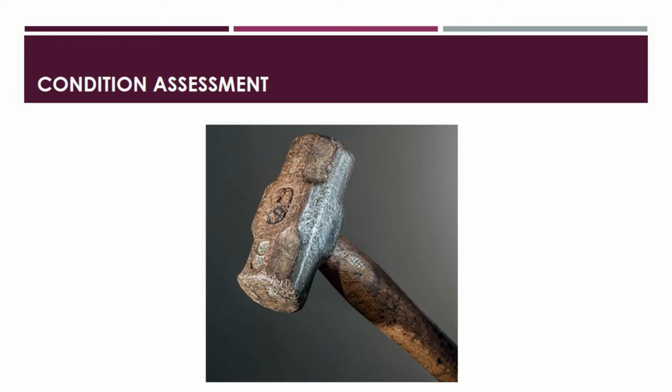Instrumented hammers record and analyze the vibration created by a hammer blow and discover patterns that indicate the severity of decay, while devices that measure the resistance of a pin fired into the pole to evaluate the severity of external rot are available. And the use of a decay resistance drill or an auger to take a sample from the pole for direct examination is also very common in the utility world.